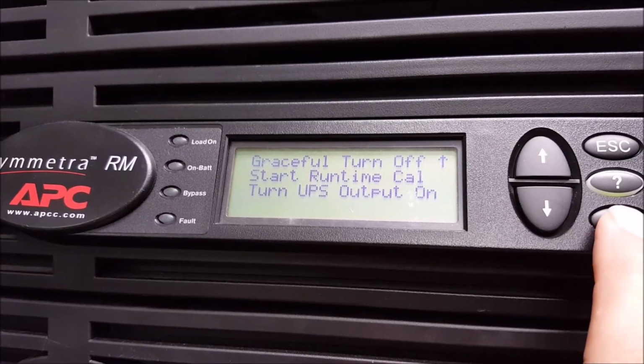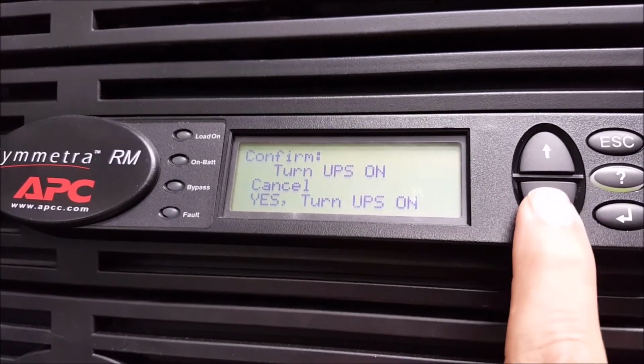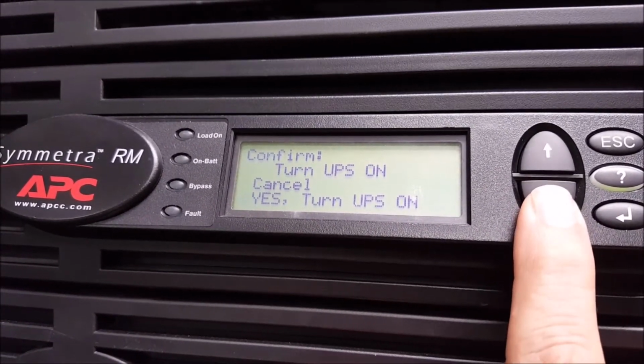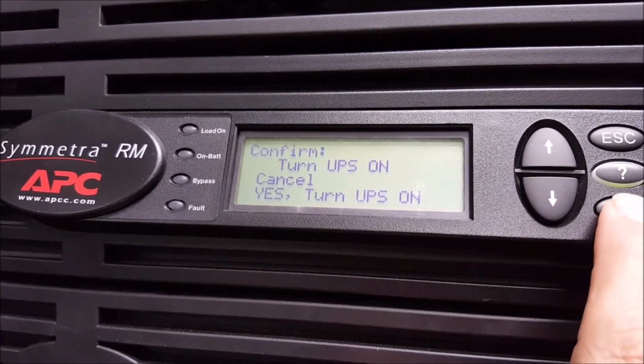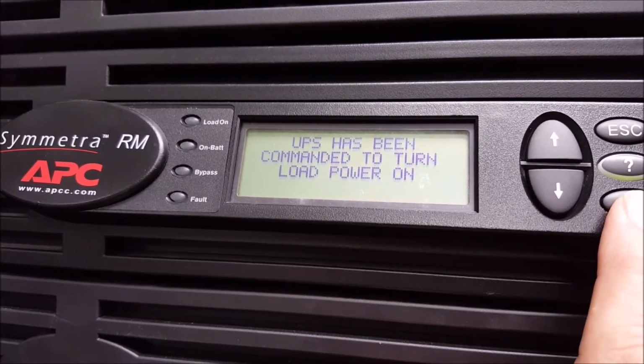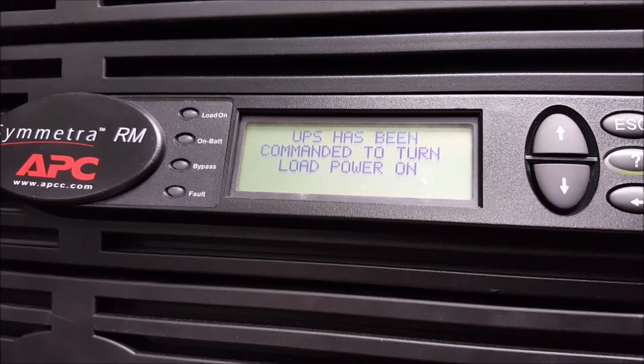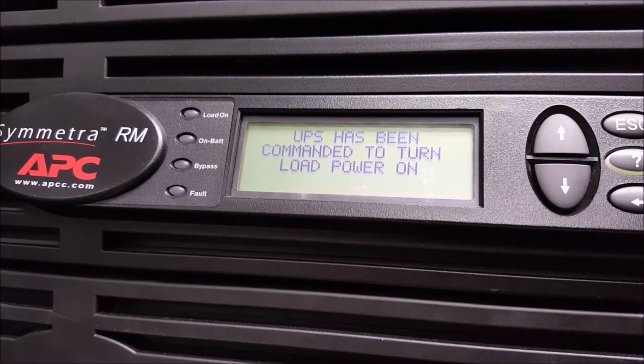Next, you'll be asked to verify that you want to restore power to the load. Use the down arrow and select the option Yes, Turn UPS On. Hit Enter on that. Immediately after selecting that option, you should get a message saying the UPS has been commanded to turn load power on. This means power is being restored to the load.